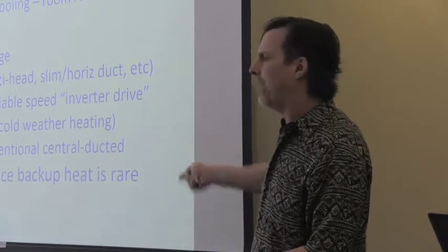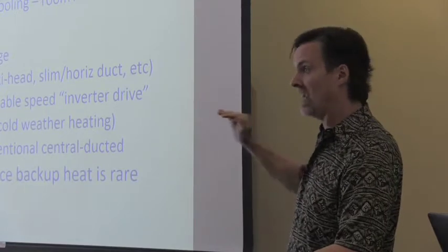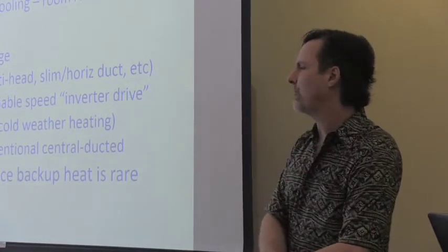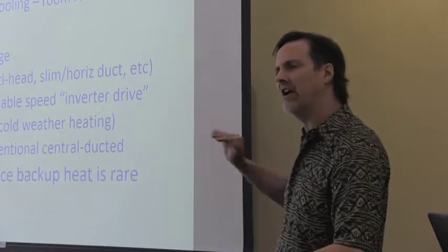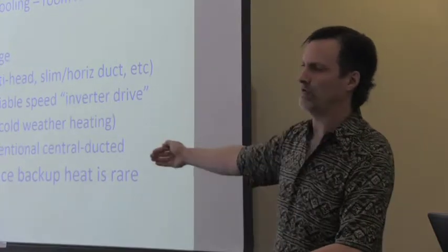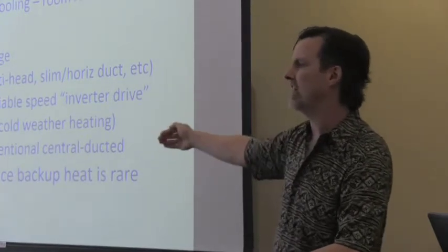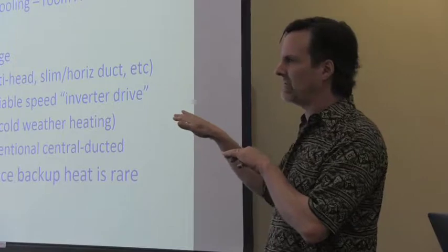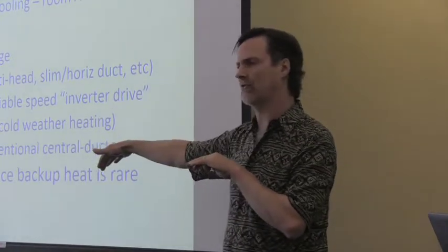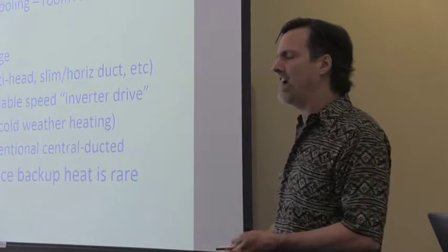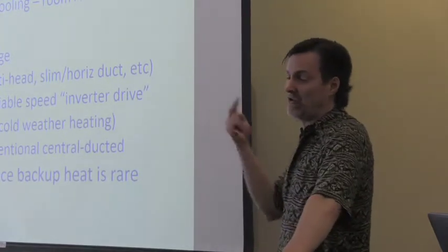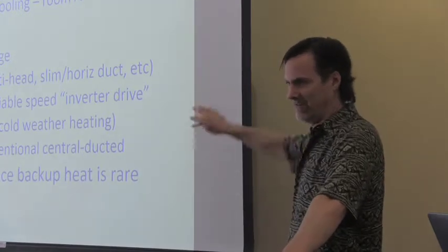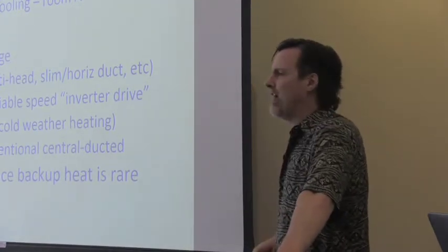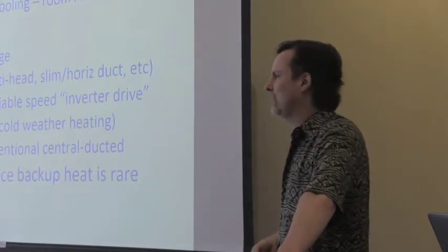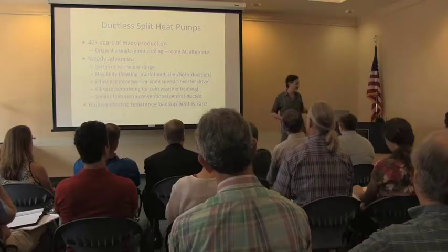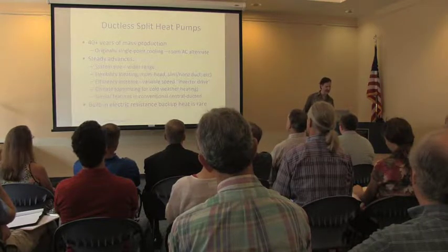Nowadays, we can get heat pumps that are designed to maintain their rated capacity, that's sort of their standard capacity at much warmer temperatures, and they'll maintain 100% of that rated capacity, sometimes down to +5 degrees, sometimes down to -5 or even -15. And then what happens after that is the capacity does start to drop off a little bit as it gets cooler, but they don't stop running. All right, my heat pumps that I installed in 2012, which are actually 2 generations ago of the cold climate technologies, it could be -25 in the morning and the heat pump is still cranking out heat and my house is still comfortable. So I can tell you from personal experience that these things actually do work.